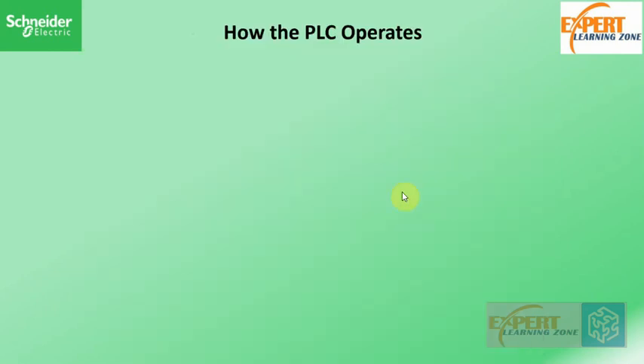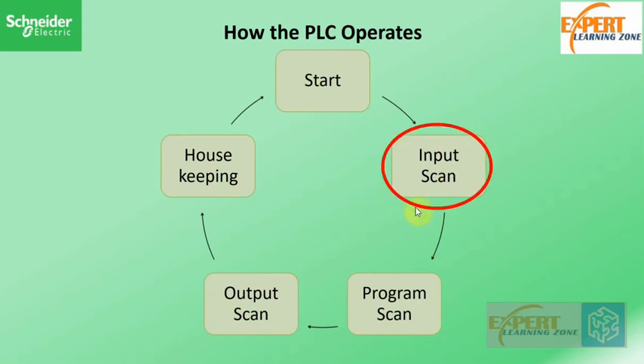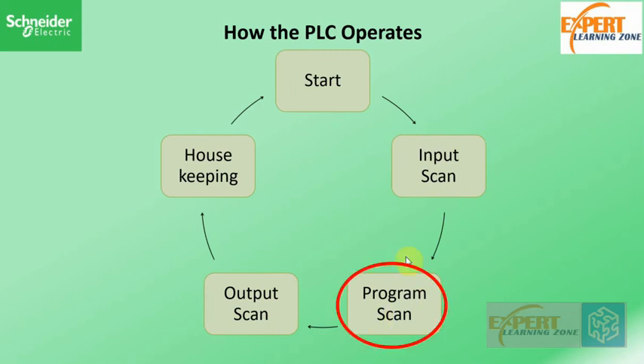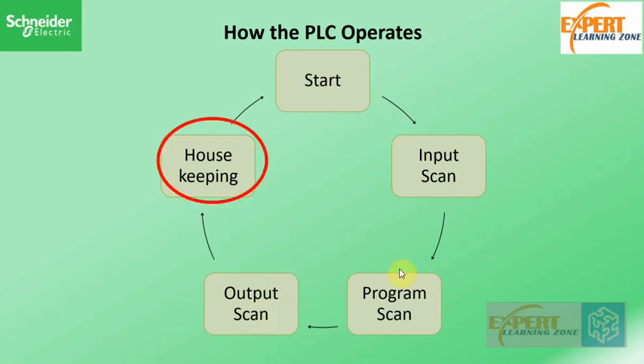Finally, we are going to look at how the PLC operates. The PLC operates in a sequential manner. When a PLC is set in run mode, first it reads the state of all the inputs — this is called the input scan. Then it performs logical operations on those inputs and updates the outputs, which are our actuators like valves, motors, and pumps. Finally, it does some housekeeping, which means it performs communications with the programming terminal and runs some internal diagnostics.